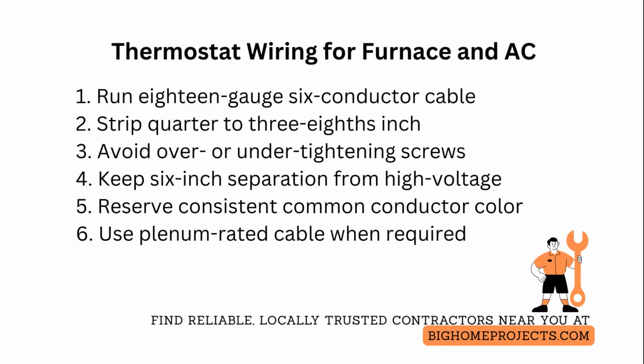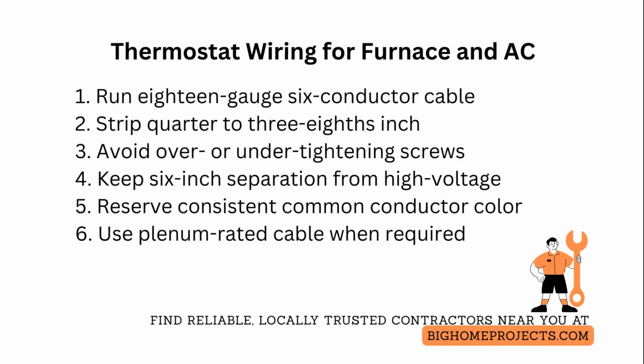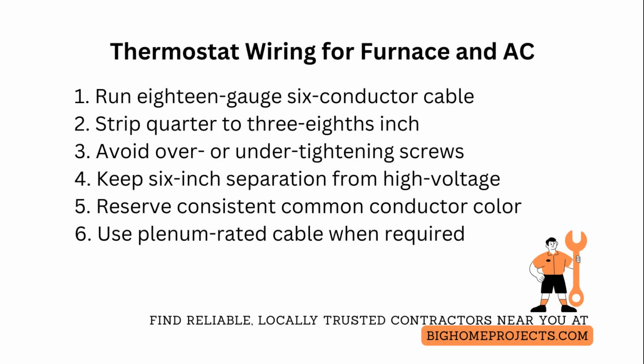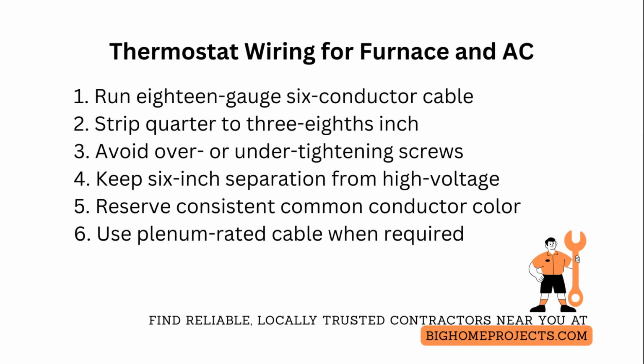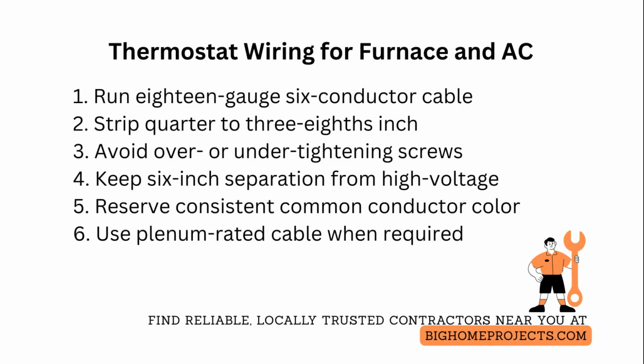Route the cable away from high voltage lines and fluorescent fixtures to prevent electromagnetic interference that can corrupt low voltage control signals. Maintain at least a 6-inch separation or cross at 90-degree angles. If your system uses a common wire for power, reserve the blue or brown conductor consistently and verify the control board's C terminal with a multimeter before connecting to avoid backfeeding.